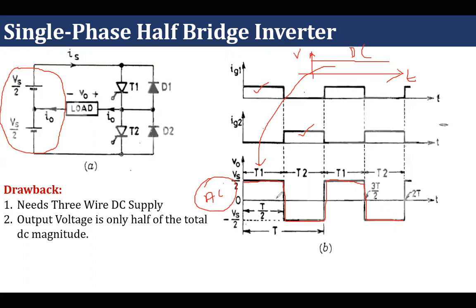If it is not sinusoidal AC, and I connect this kind of output to, let us consider, a fan, will the fan rotate? Yes, the fan will rotate. It will rotate due to its fundamental component, and the rest of the harmonics will generate problems in the motor. That means it will create heat in the winding, and it will create vibration in the motor. That we will see when we do Fourier analysis. Again, we'll come to this point.